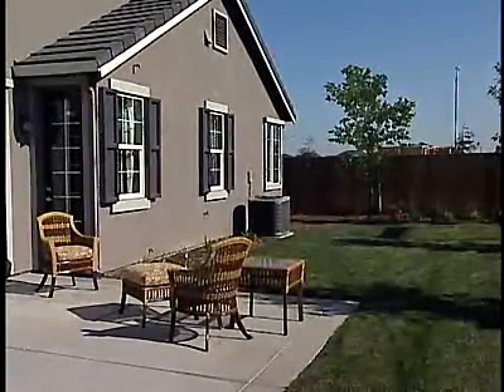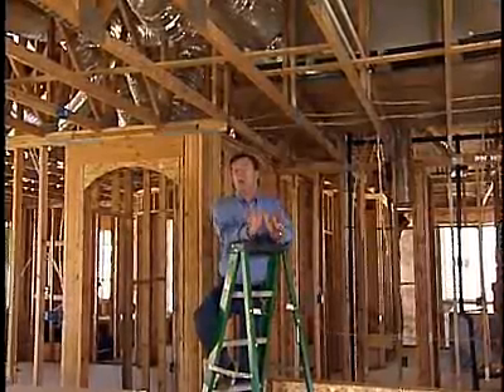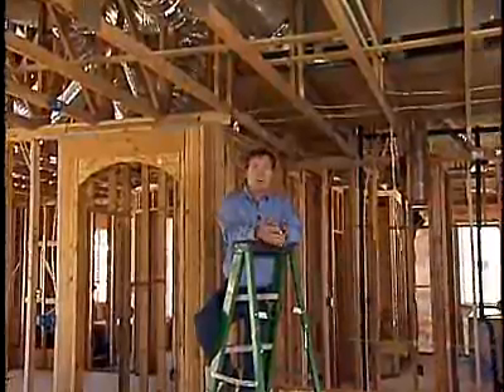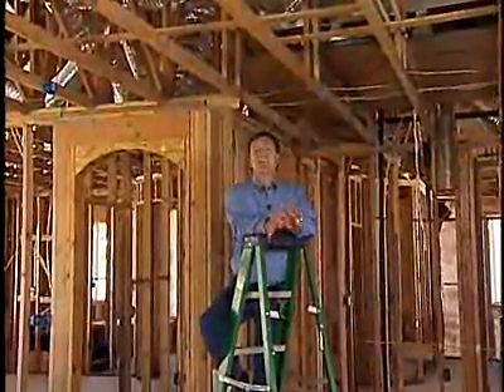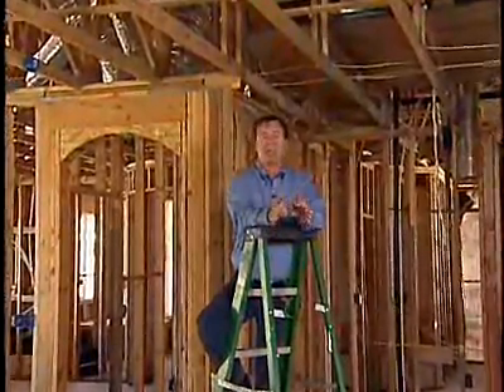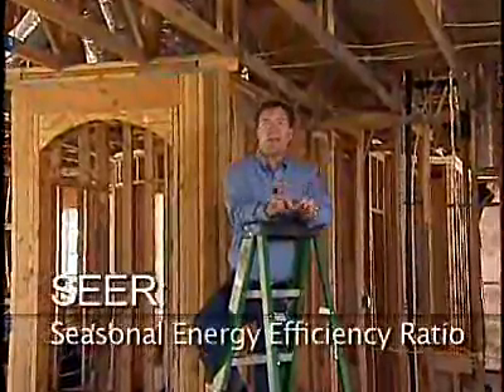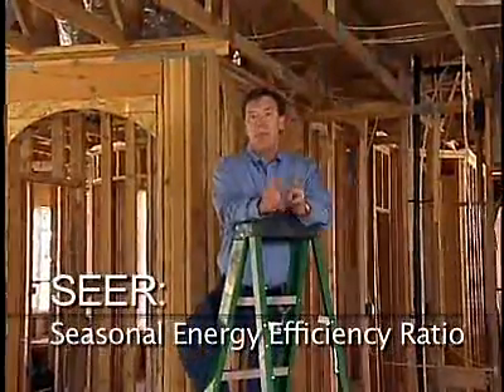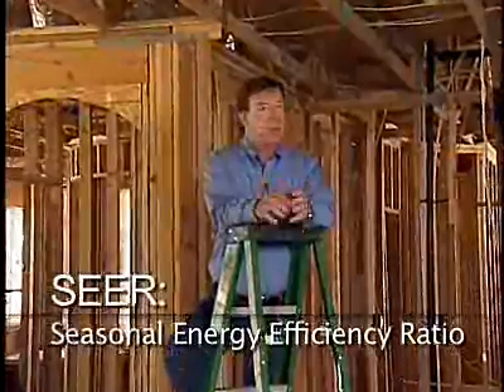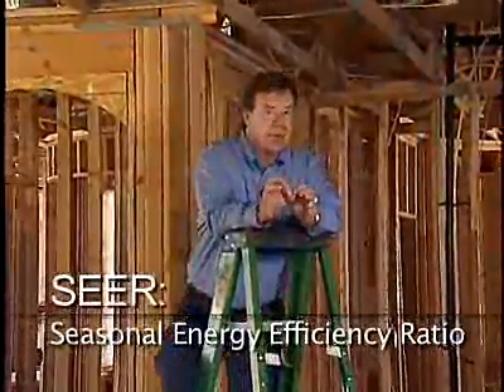The terms that we use to rate the efficiency of a heating and cooling system are as follows. Typically we rate the air conditioning systems as its SEER, S-E-E-R, its seasonal energy efficiency ratio. And the minimum SEER, a piece of equipment that you can put in a home today, is a SEER 13. So for example, if you had a SEER 6 in a home that was say 20, 25 years old, and you went to a SEER 12, it would be double the efficiency or cut your air conditioning costs in half, for example.